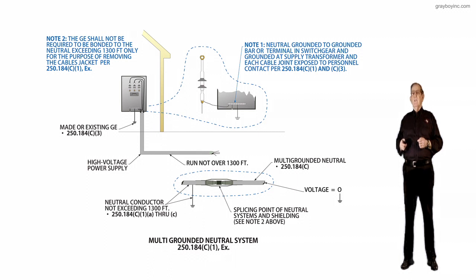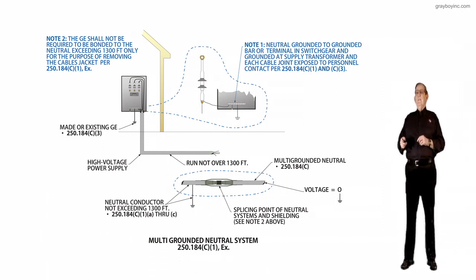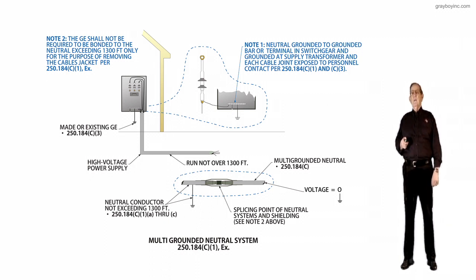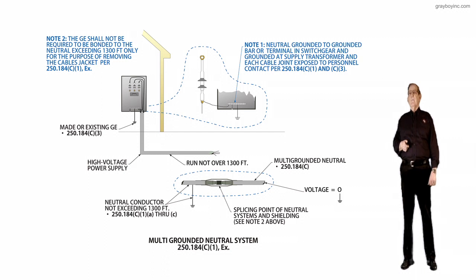And the fourth thing I'd like to call out is the call out pointing to the splice there at the cable, the splicing point of the neutral system and shielding, we'd need to see 2 above. And when we looked at that, then we got a good feel for that. And then notice the other call out is multiple grounding type neutral, 250.184(C), and the arrow is drawn to that. And then the voltage is basically 0 there. But notice that we do not ground in there at 1,300 feet, as the purpose of change called out.